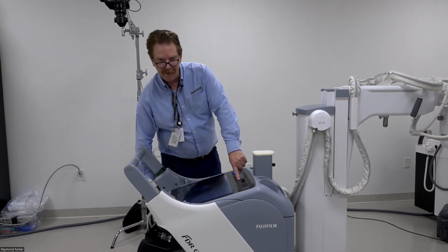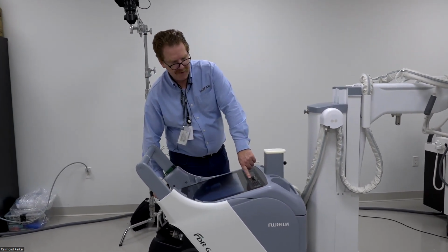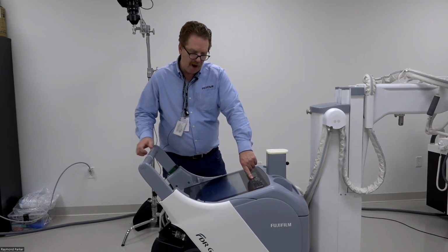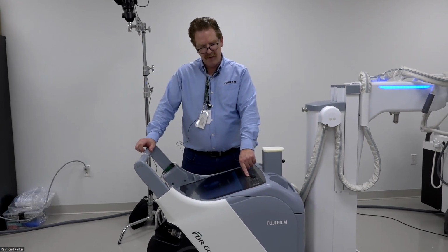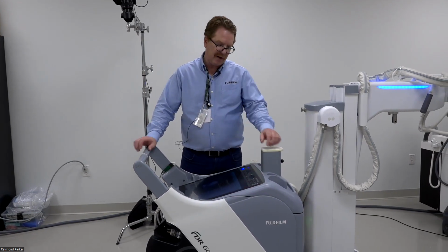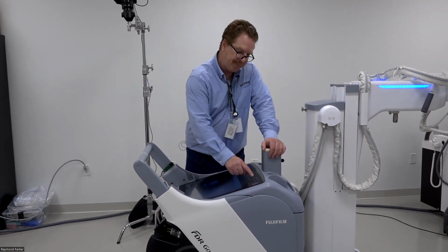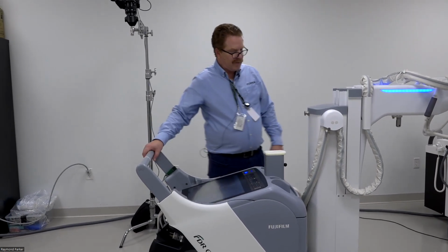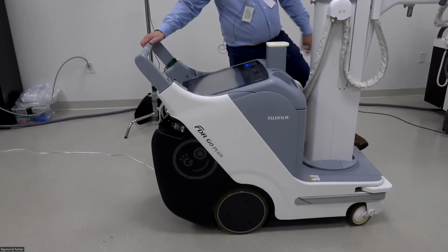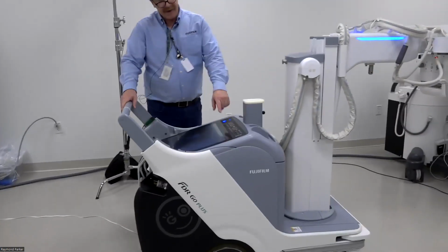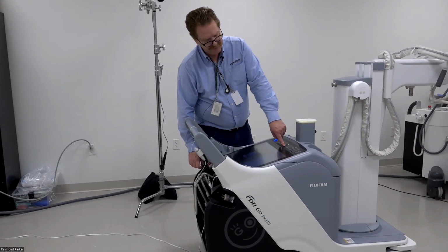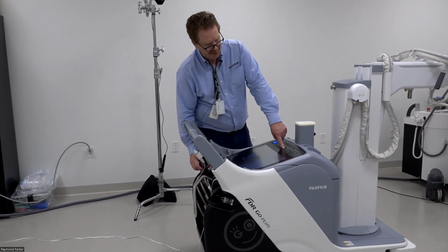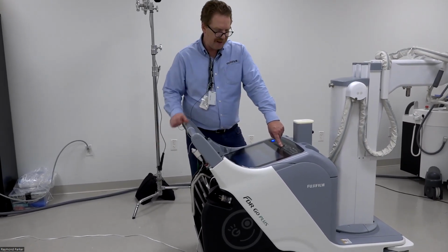press the collimator light button on the generator, and turn the key on. Hold that till you hear a beep. Once the beep is heard, put in your password, 1234, and you'd be able to drive without the beeping sound. And that keystroke was turn the key off, press the collimator light button, turn the key on.